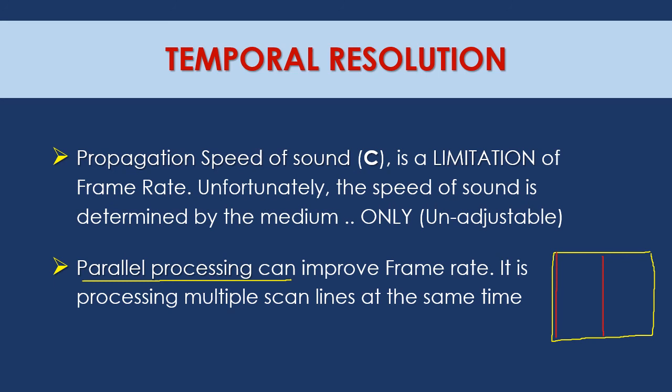At the end, when I get the scan lines filling this half, the other half is filled at the same time. That's why we call it parallel processing, which will cut the time of the frame in half, or by a third at least in some cases. In this way, parallel processing greatly improves the frame rate.